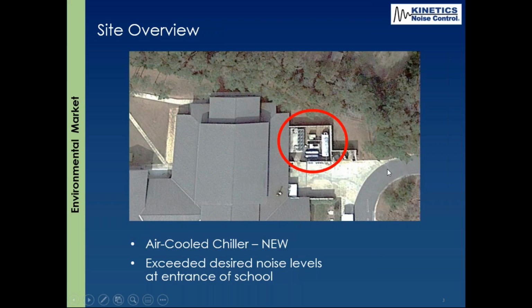Now this walkway that you see coming from the driveway or drive-through is one of the main rear entrances to the school. Although it wasn't the main front entrance, there was still a lot of deliveries, both materials and food, through this back entrance, and most of the school teachers would come in through it. Right at the bottom here, right as you go into the school, there's an opening to that equipment yard. They were exceeding the noise level there of actually 85 dBA at this particular spot when that chiller was running 100% load. So those were the things we needed to be concerned with.